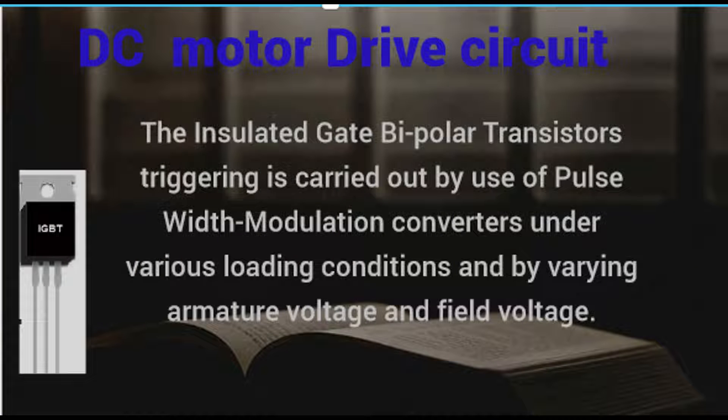IGBTs are available with higher current ratings and are rugged, but have slower switching speed. Their lack of an internal reverse-recovery diode means you must find an IGBT co-packaged with a diode matched to your application. The IGBT's triggering is carried out by use of pulse-width modulation converters under various loading conditions and by varying armature voltage and field voltage.